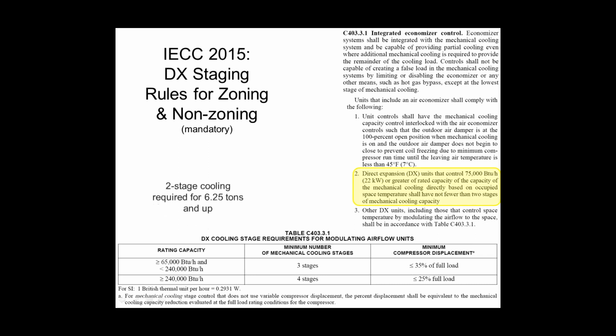Note number 2, if you have a direct expansion system that is 75,000 BTUs and up, so 6.25 tons or greater, and the capacity is directly based on occupied space temperature, you have to have no less than 2 stages of mechanical cooling capacity. So basically you got a rooftop unit or an air handler or a split system that is controlled off of a single zone thermostat, you got to have 2 stages. You're not allowed by code to put in a 7.5 or 10-ton single stage unit.